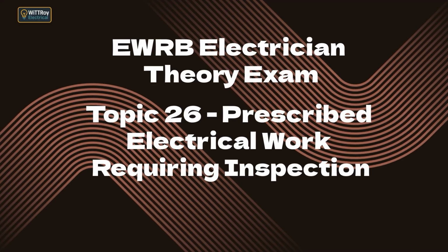Examples of work that must be inspected include mains earthing or bonding work, work on main switchboards that affects the main system, work involving mains where the neutral or earthing arrangements have been altered, installations in medical cardiac locations, and installations in hazardous areas. These are high-risk prescribed electrical work listed in the regulations. The electrician must complete all their tests and issue a certificate of compliance, but the installation cannot be livened until the inspector has completed their inspection and signed the inspection documentation.